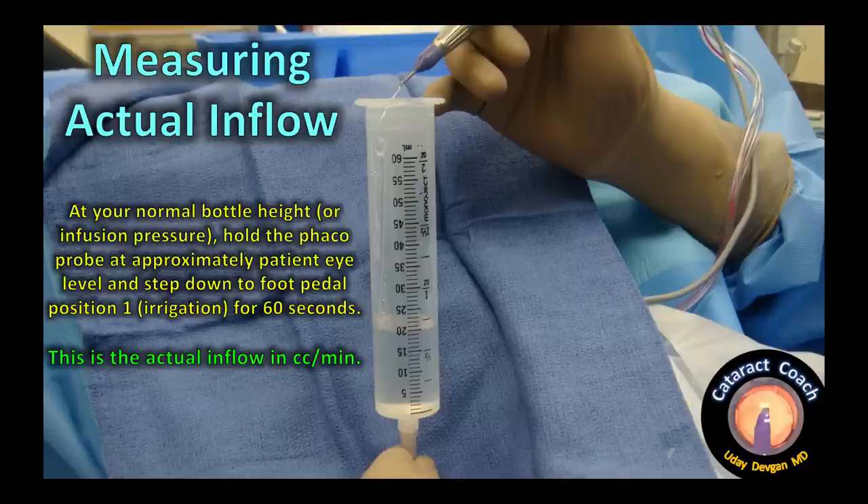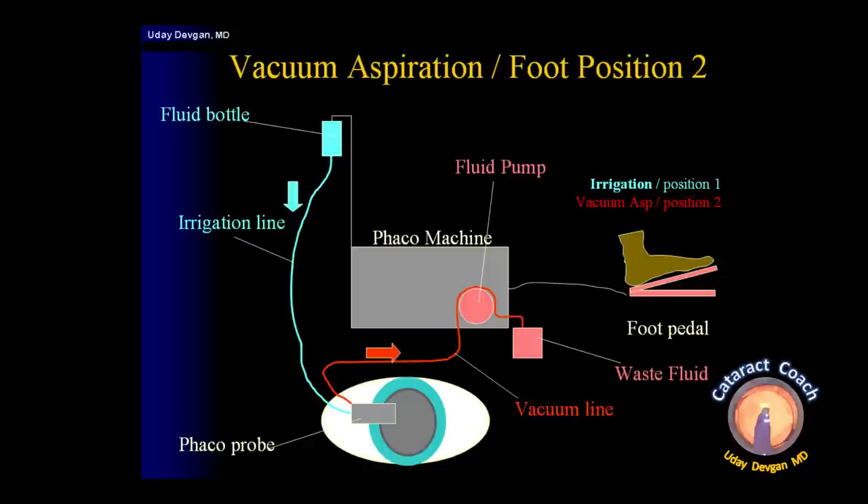How much fluid is brought into the eye depends on your setup, and you actually need to measure it — 99% of surgeons don't do this. At your normal bottle height or infusion pressure, hold the phaco probe at approximately the patient's eye level, then step down to foot pedal position one for 60 seconds. Measure the result with an empty syringe to find your actual inflow of balanced salt solution in cc's per minute. We need to know this to ensure inflow is sufficient to keep up with outflow.